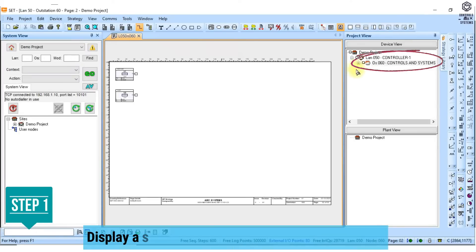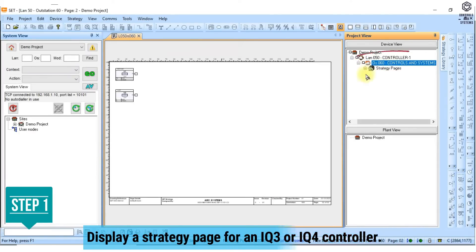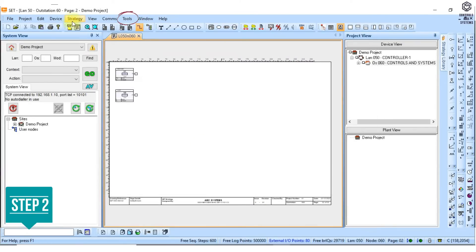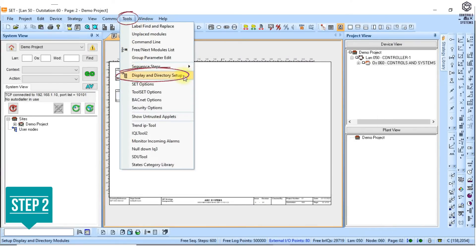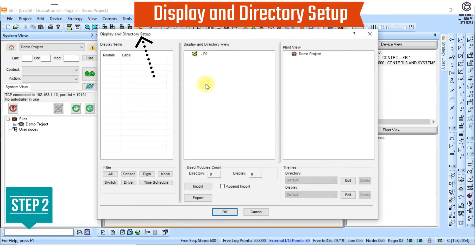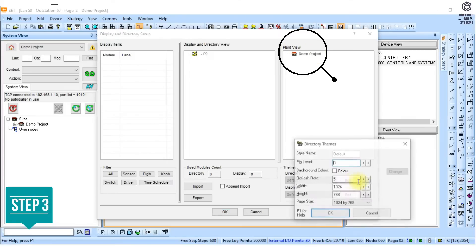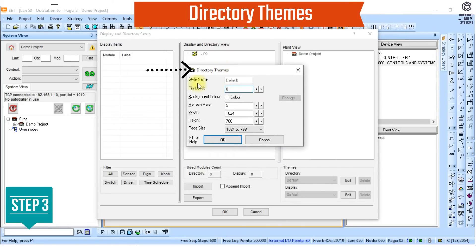To set up directory module parameter defaults: 1. Display a strategy page for an IQ3 or IQ4 controller. 2. Click on this symbol, or go to the tools menu and click display and directory setup. The display and directory setup dialog box is displayed. 3. In the plant view area click edit to the directory box. The directory themes dialog box is displayed.